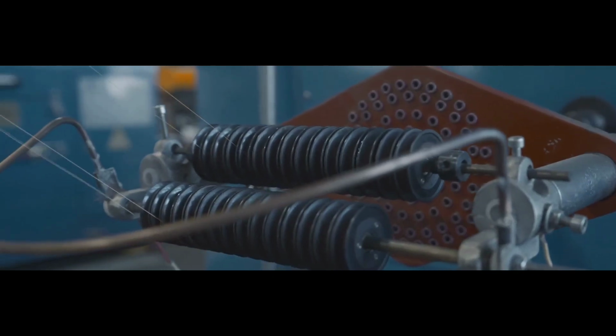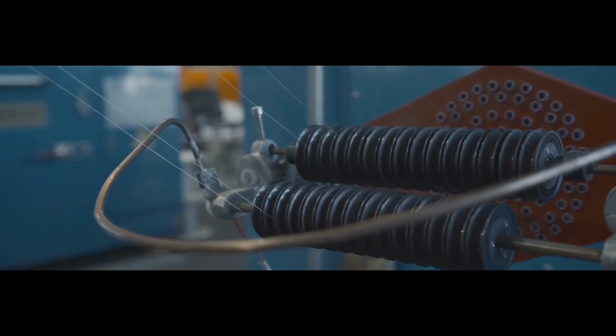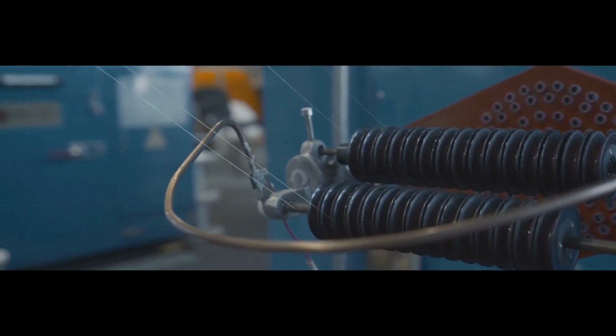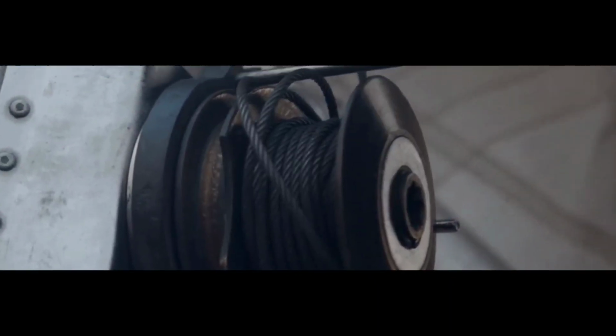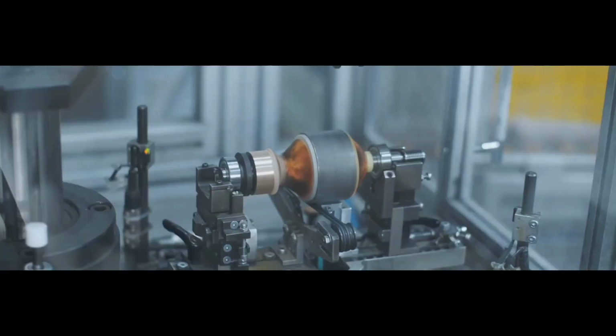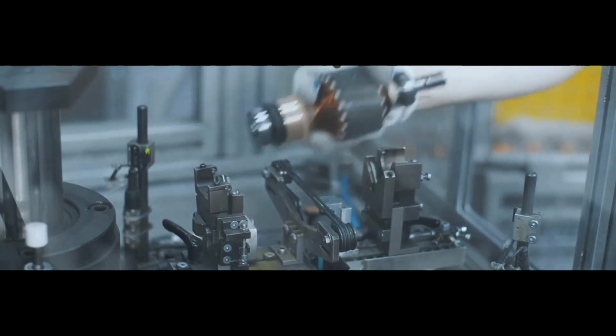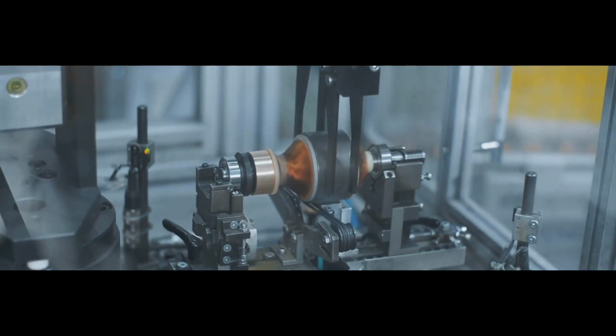To solve this, engineers use compensating windings and interpoles. Compensating windings are placed in the pole faces to cancel out the unwanted magnetic fields, while interpoles are small auxiliary poles that help with smooth commutation, reducing sparking and keeping the motor running efficiently. These clever engineering solutions keep DC machines both efficient and reliable. The right winding method, combined with smart design, ensures that the machine delivers power smoothly and safely. That's how we keep the sparks at bay and the motors spinning strong.